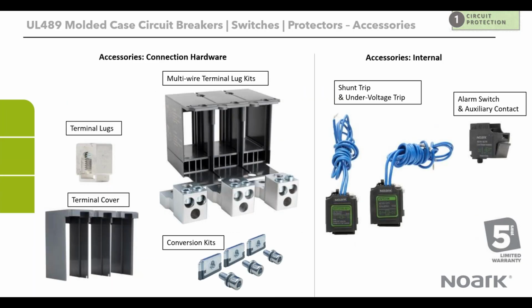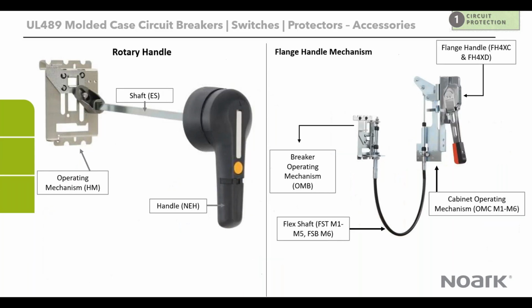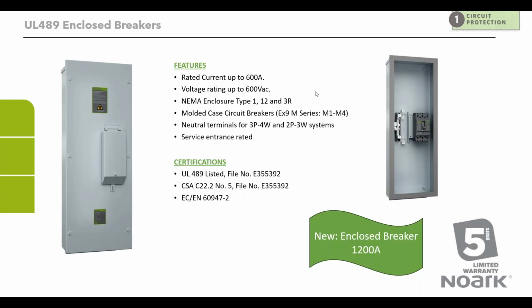These are summarized accessories, because we have way more than this, but basically you can see the shunt and the undervoltage, the multi-wire terminal lug kits, and conversion kits that allow you to convert from a lug terminal to a bus bar connection. We also have rotary handles and flange handles as well. And we did mention earlier on that we have enclosed breakers.